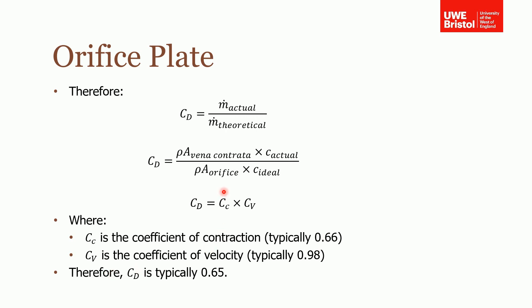So therefore when you times these two together you get the discharge coefficient. Times these two together it's typically around 0.65. The discharge coefficient is typically 0.65 for an orifice plate meter.